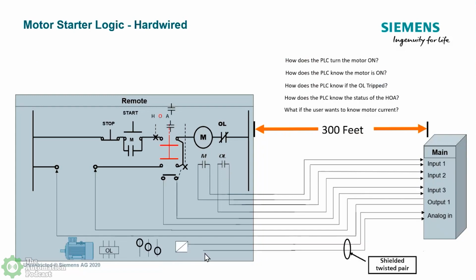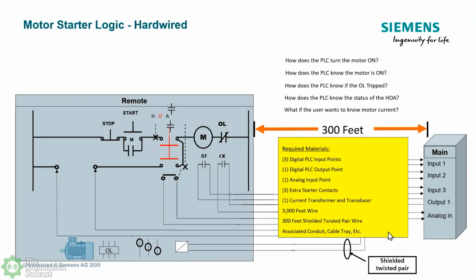If you're listening and not watching, you end up for this one motor starter logic hardwiring it to the PLC, you're using a lot of I/O. Correct. Yep. And then that I/O takes up places. That's terminal blocks. So you're landing a lot of stuff for just one simple turn on and off motor. But this is what we seasoned individuals did back in the day. And then notice here that we've put a CT in so we could see the current, bringing it in as an analog input. And then here's kind of the bill of material.